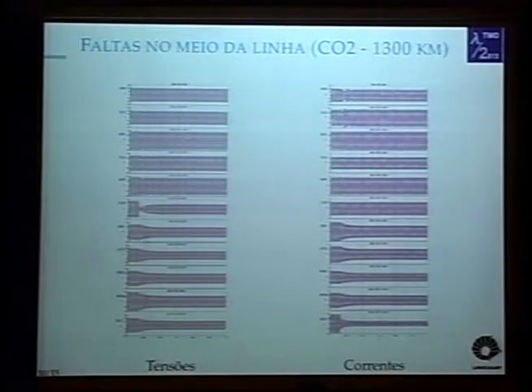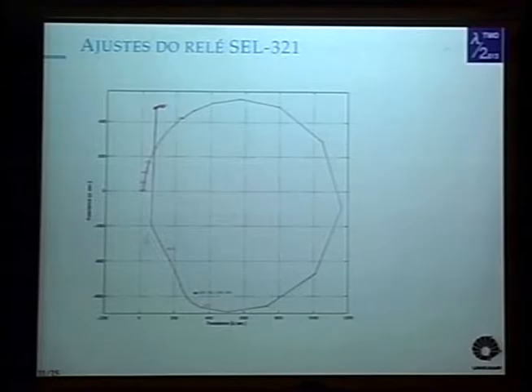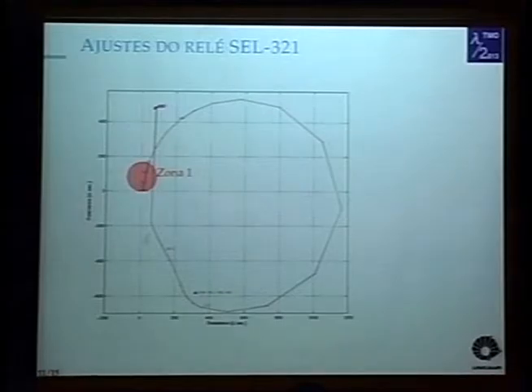So it's possible to see that identifying the three-phase fault in the middle of the line is very complicated, just using measurements in the substation of Serra da Mesa 1. So here we have the adjustments we could make for relay SEL-321. We used zone 1 to cover the beginning of the line, zone 2 with the maximum reach of the relay to cover this region. And we also used something that would not normally be used, the reverse zones 3 and 4, to protect the final segment of the line.